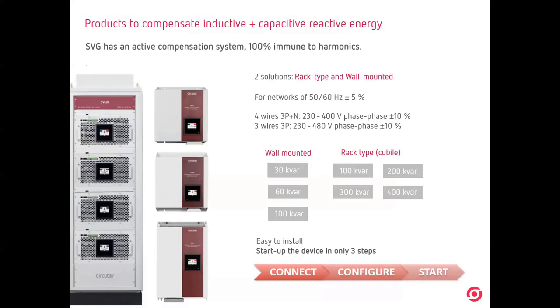But what happens if we have capacitive in our installation? The typical cases are, for example, data processing centers, systems with a lot of LEDs, or systems with a lot of UPS. Well, you will have a lot of capacitive. If you have penalties, you cannot connect capacitor banks, obviously, and you cannot connect a reactor because it's very expensive. The best way is to use something called an SVG, static var generator. This is an active compensation, 100% immune to harmonics.